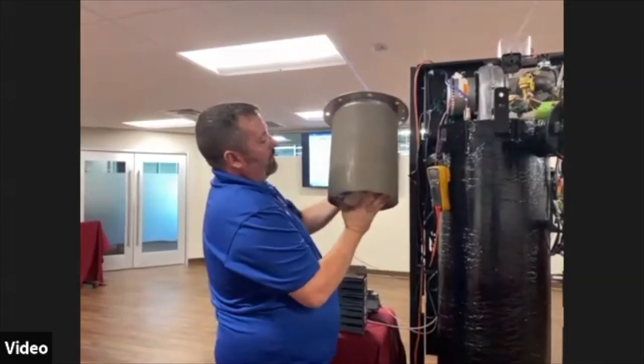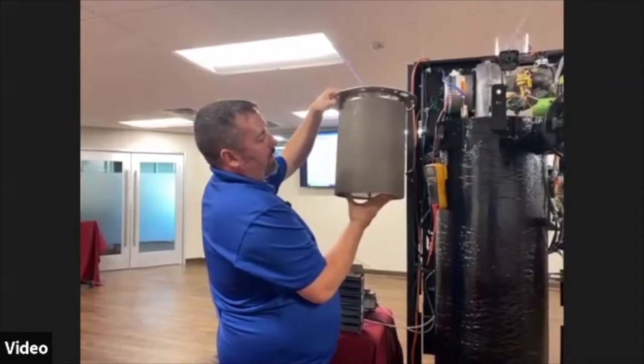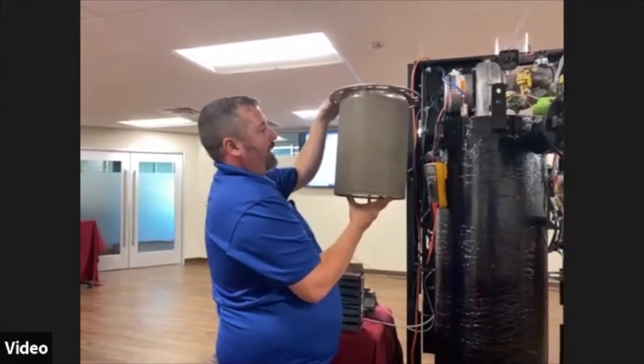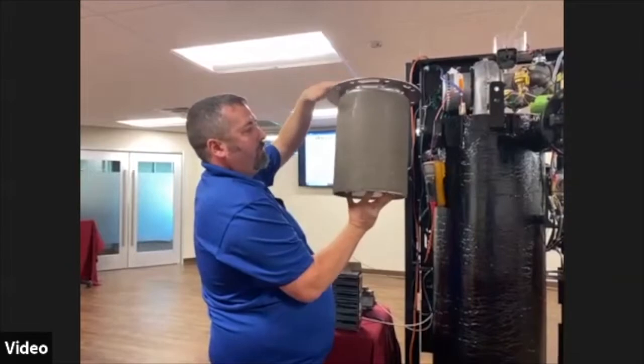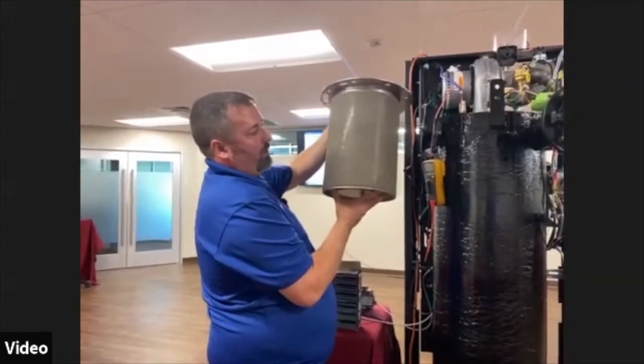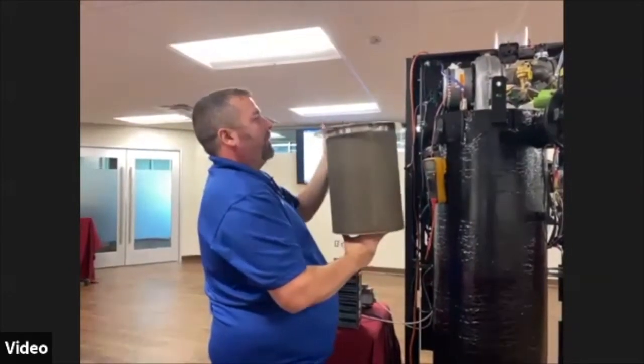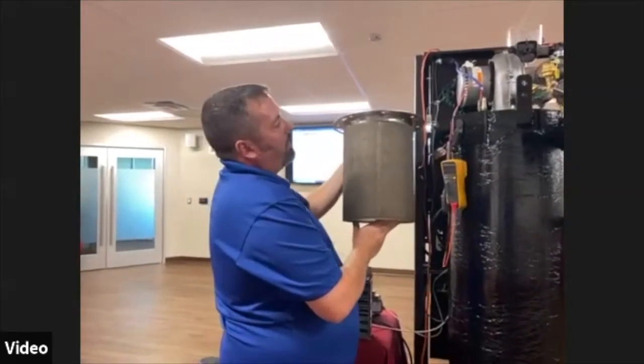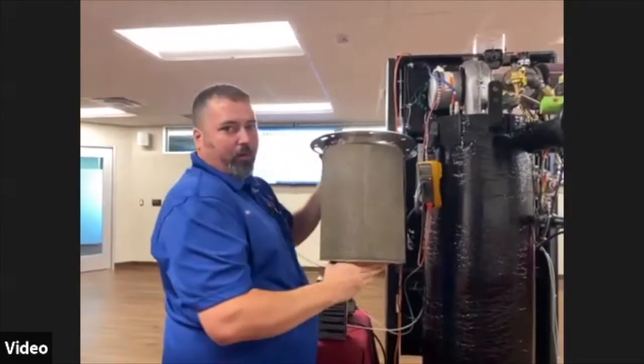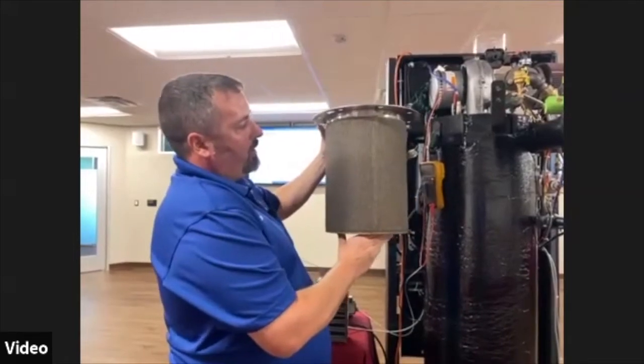When you pull it, you want to inspect it, make sure there's no gashes, no scratches, no holes. Anything like that can cause a hot spot and cause your efficiencies and your COs to go up. Your flue gases won't be burning properly. Generally, blow it out with compressed air, nitrogen, something along those lines.